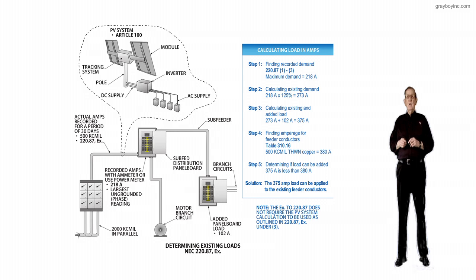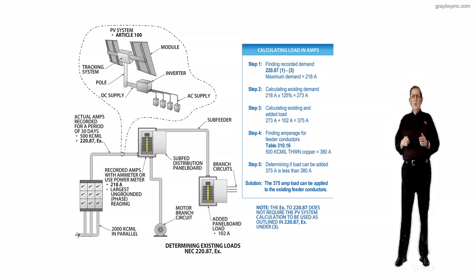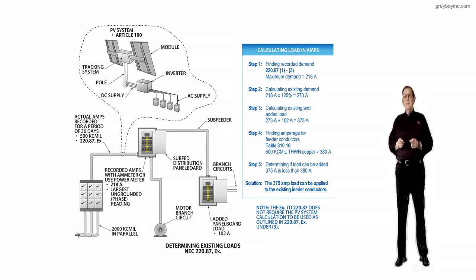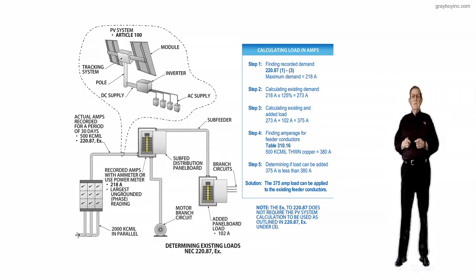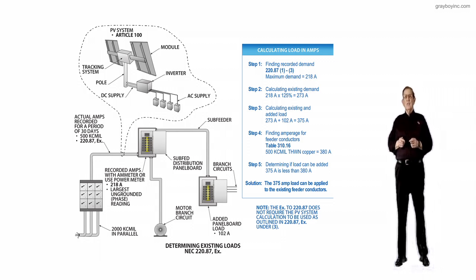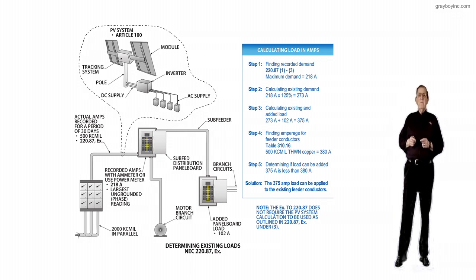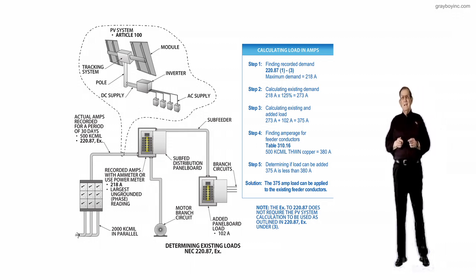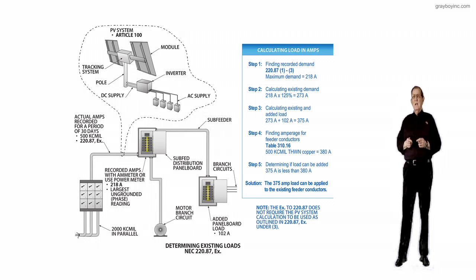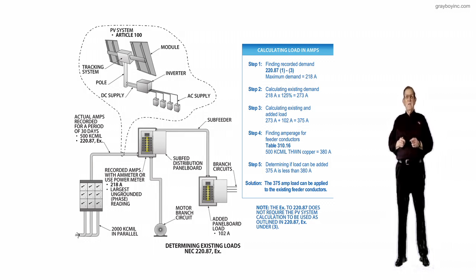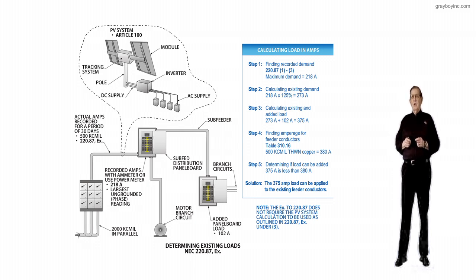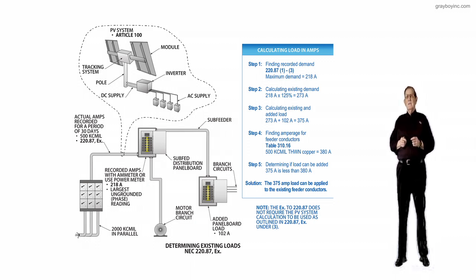Additionally, there is no effective way to determine the contribution from these systems, so the peak demand could not be calculated, and there is no easy way to describe a meter scenario that could be used to obtain the actual peak demand. Therefore, an exception is added to indicate that the calculation method shall not be used if the feeder or service has any renewable system or employs any form of peak load shaving.